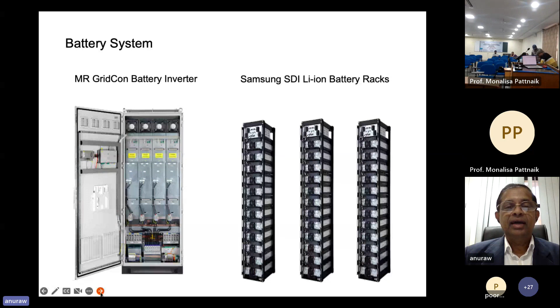You can see the battery system can operate very flexibly in the first, second, third, or fourth quadrant as required. Depending upon the load requirements or charging requirement, we will program it, and the master controller will give directions for the battery systems to operate.